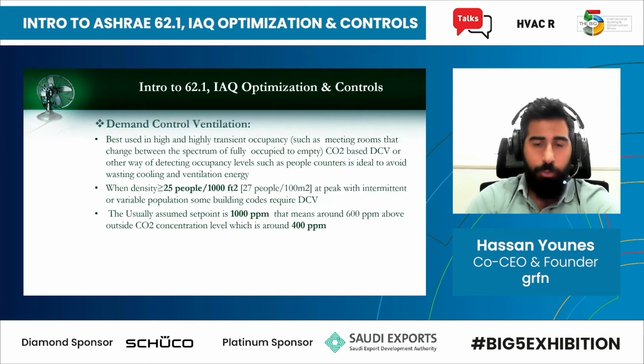And in that case, we'd save some energy. Now, it's not recommended to do demand control ventilation during the pandemic, so we prefer to turn that off when we have an airborne transmission possibility, which is the case with the coronavirus. And it's recommended to use DCV whenever you have more than 25 people per 1,000 square feet, and you have this movement and the number of people is not constant in that particular room.